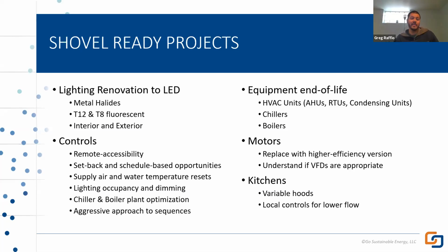Another one to look for is light-to-heavy controls upgrades. Ask yourself if your controls can be accessed remotely. Can they set back or schedule your equipment more aggressively? Can you change the supply temperature of air or water in your building systems? That can frequently have a supply temperature reset, for example, based on outdoor air. There are lots of ways to look at how energy is used from a water and energy flow perspective.